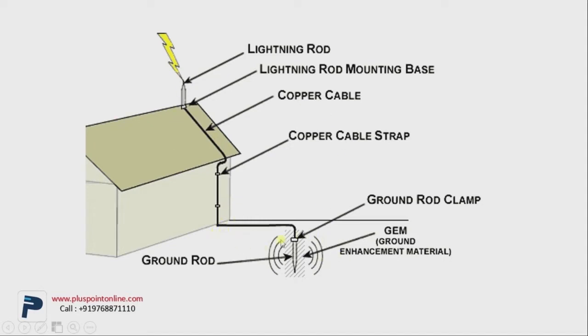In grounding, there's a ground rod which is also known as the copper rod or the copper plate. However, for lightning protection, the copper rod is not as effective as the lightning rod. There's also something like a clamp and grounding, which I'll explain in detail later. All these materials are used for the lightning protection.